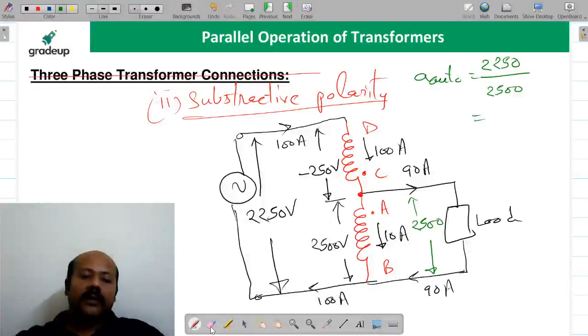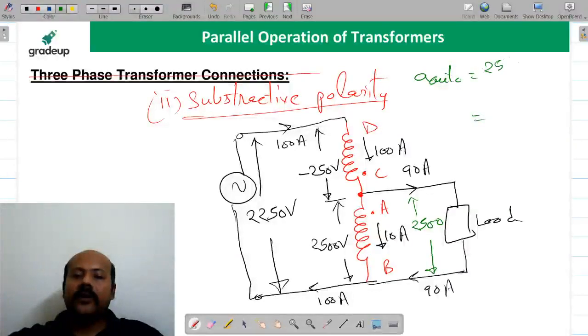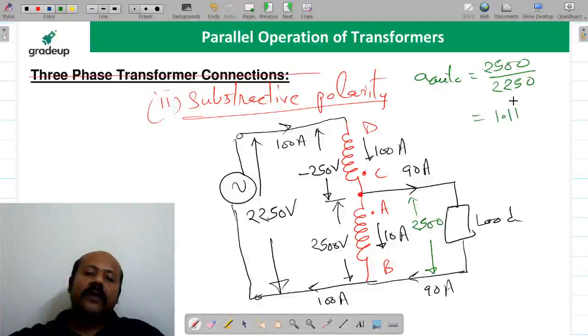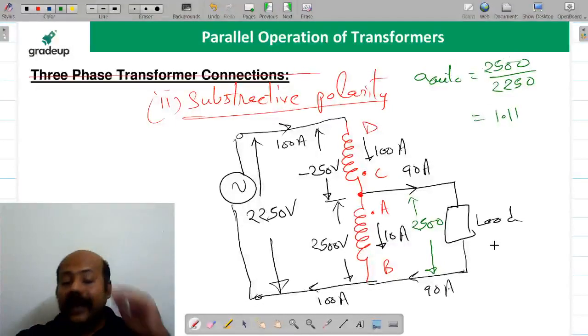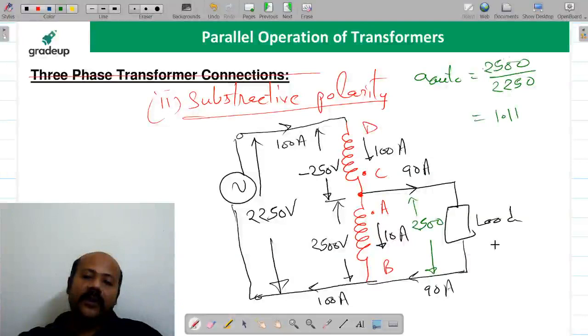Sorry, just reverse it - I had written low voltage upon high voltage. Reverse it and write it as high voltage upon low voltage. So this is 2500, the high voltage, and the low voltage is 2250. If you simplify this, you again get a value close to one for the autotransformer turns ratio, so it is a good option.